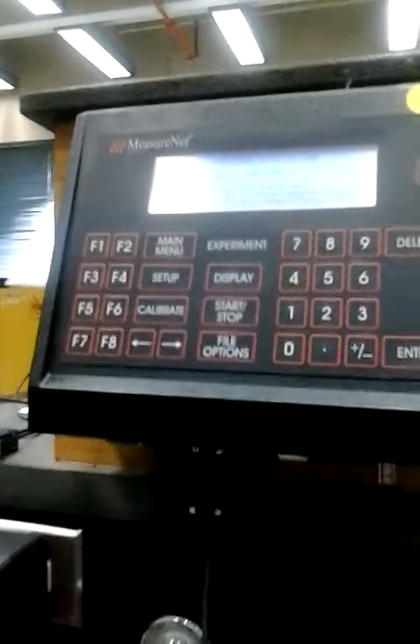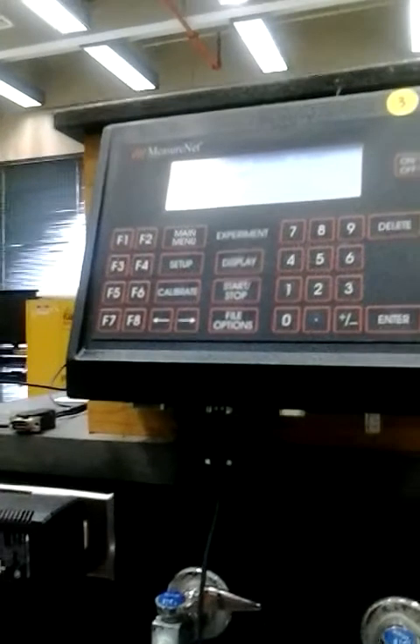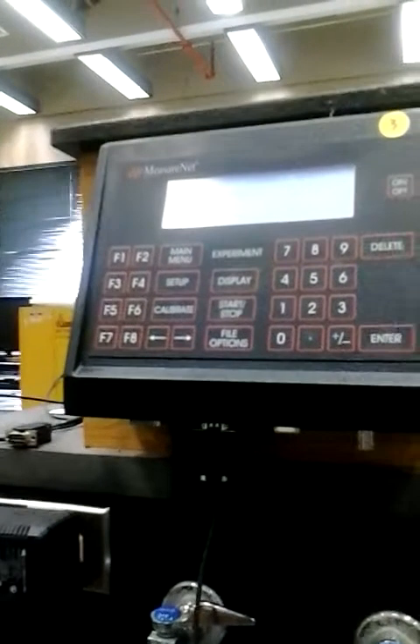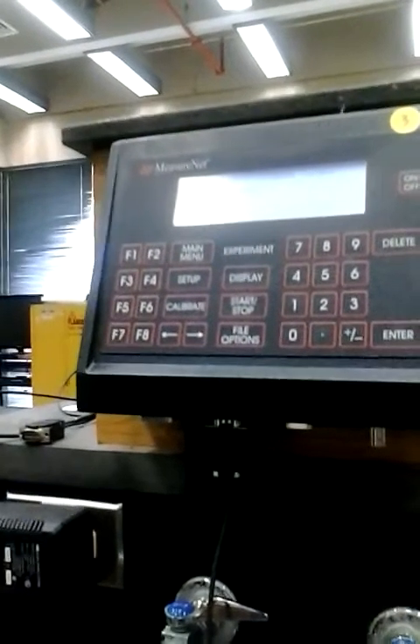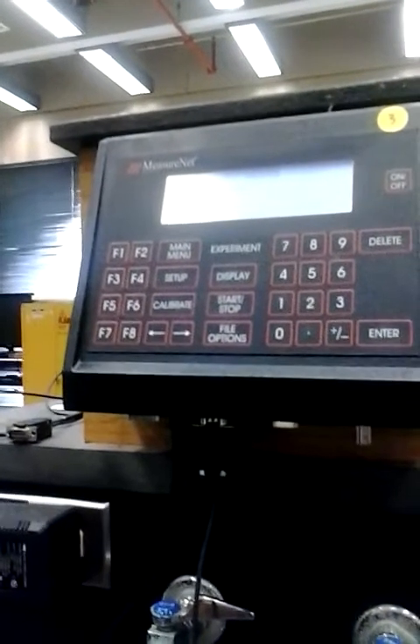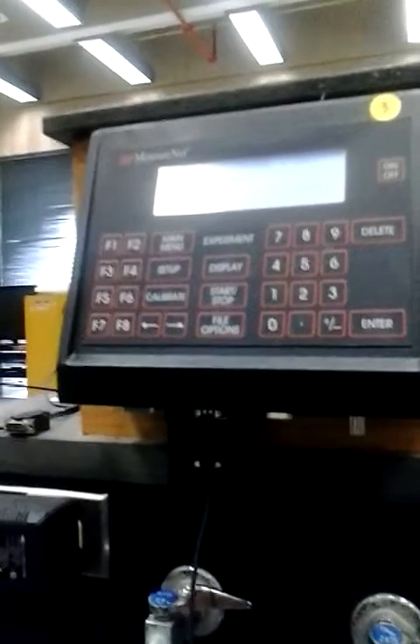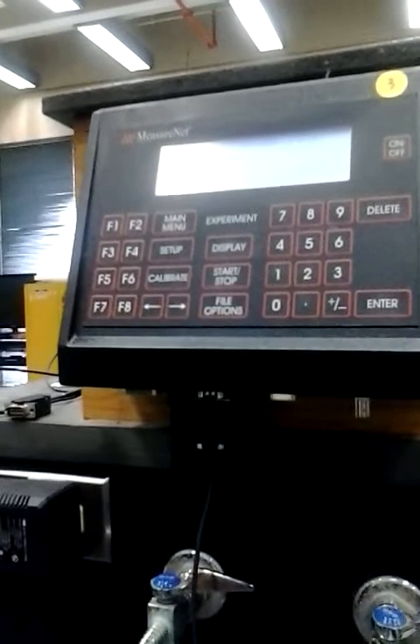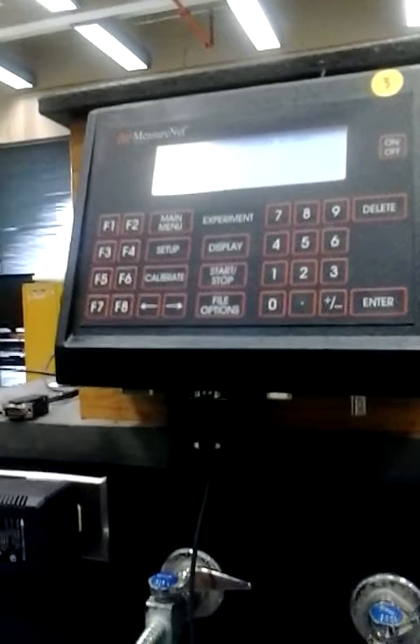The first thing we need to do is calibrate the probe. Hit calibrate and it's going to ask you to enter the barometric pressure in Torr. You can look on weather.com to find the pressure — it'll be in inches of mercury, and then just convert it to Torr.